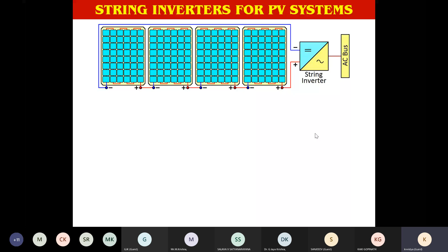Such inverters are known as string inverters. Now, string inverters are very popular. Even in our house we have a string inverter, because it is relatively less expensive and it is very simple also. But it has a drawback. The drawback is, since all these modules are connected in series, if any module fails, the entire string will become useless. The entire power generated by all the modules will be lost because of a problem with a single one, because of the series connection.